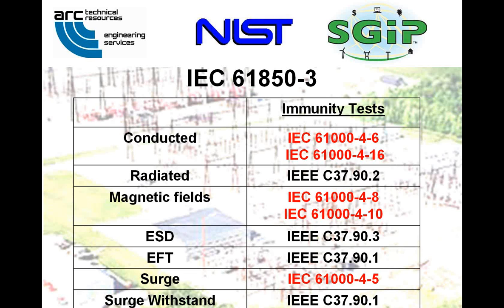61000-4-5, surge. There was no indirect lightning test in the IEEE. And ring wave and damped oscillatory waves were already covered by C37.90.1 based on 61000-4-12. These 5 gap immunity tests, which I just showed you in red, are referenced in the new 1613.1-2013.